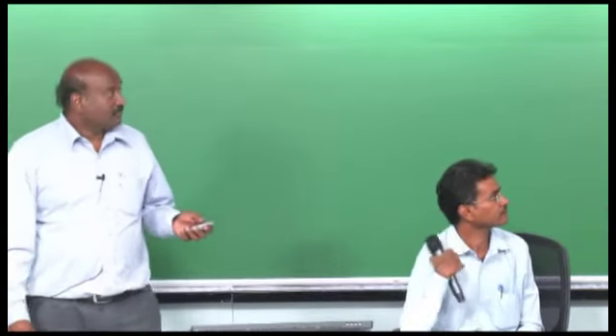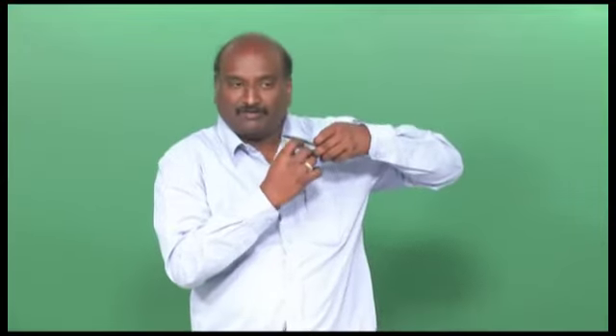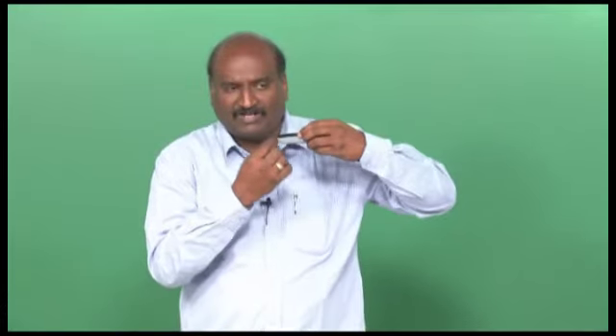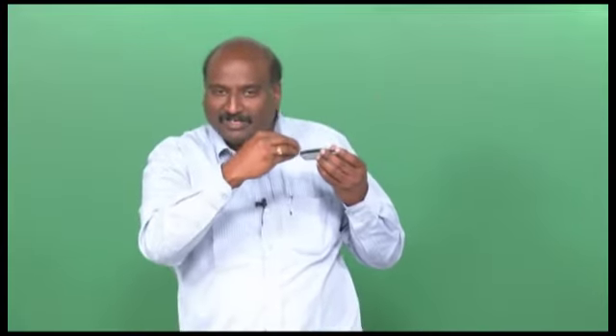Gas groups are classified into three: 2A, 2B, and 2C. 2A includes propane, 2B includes ethylene, and 2C includes hydrogen. There is a reason for specifying gas groups — related to the maximum experimental safe gap (MESG). When you design an equipment enclosure, you cannot say it is completely sealed. There is always a gap of less than 1 mm or 0.5 mm, and for a vapour, this gap is more than sufficient for it to enter inside. That is what is called the safe gap for those products.